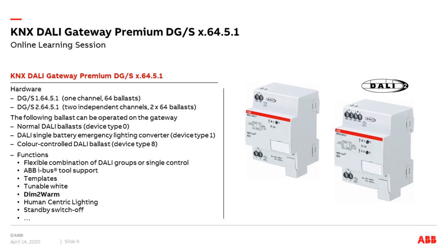Both DALI Gateway Premiums have identical functions but different numbers of DALI outputs. The DG/S 1.64.5.1 has one DALI output and the DG/S 2.64.5.1 has two independent DALI outputs. Normal DALI ballast device type 0, DALI single battery emergency lighting converters device type 1, and colored control DALI ballast device type 8 can be connected to both. The gateways offer extensive functions including templates, tunable white, human-centric lighting, Dim2Warm, flexible group or single ballast control, and ABB i-bus tool support.